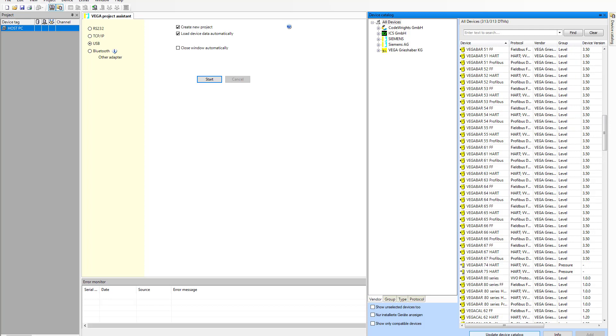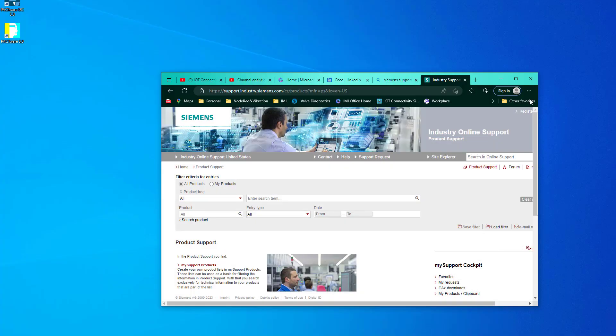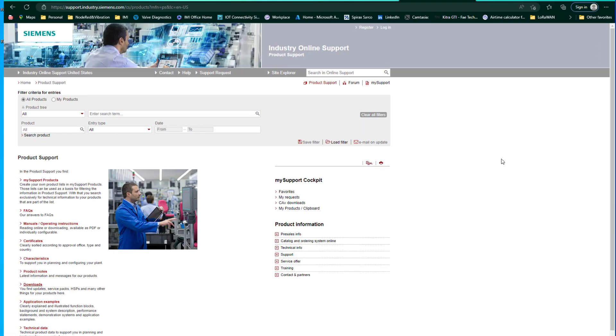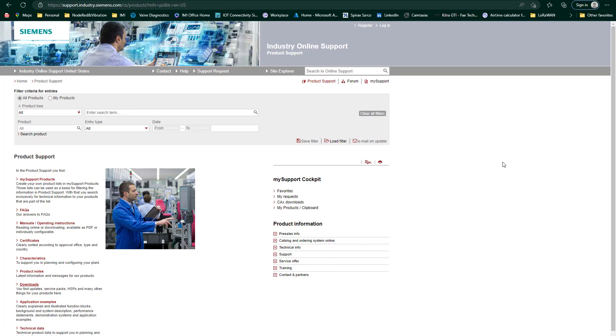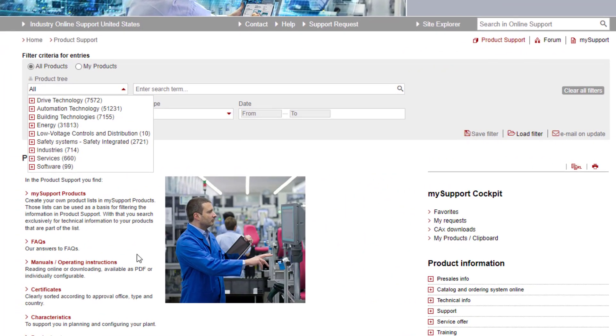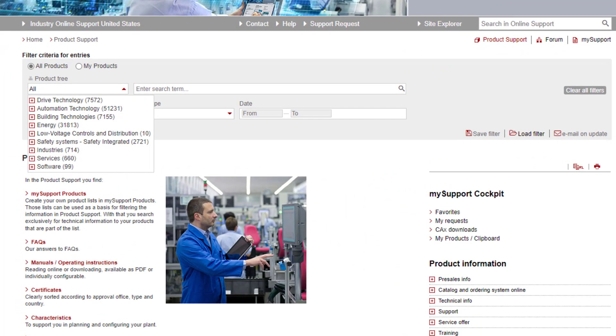Siemens is slightly different. What they have done, which is quite clever because you get the same functionality across different types of tools like Simatic PDM and PACTware, is they have created an EDD converter and that is called SITRANS DTM and it can be quite difficult to find.